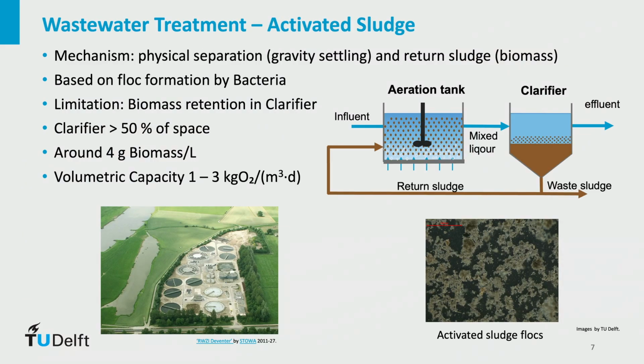While trickling filters are still used with modern media, the activated sludge process dominates wastewater treatment nowadays. Developed over a century ago, this process mixes wastewater and bacteria in an aerated tank. Instead of growing on the surface, bacteria form flocks, clumps of biomass that can be settled out by gravity after the treatment. This settling process effectively limits the treatment capacity. Flocks settle slowly at about 1 meter per hour, and require large so-called clarifiers to separate the biomass from the treated water. Also, the settled biomass has a low concentration, limiting the concentration in the aeration tank.